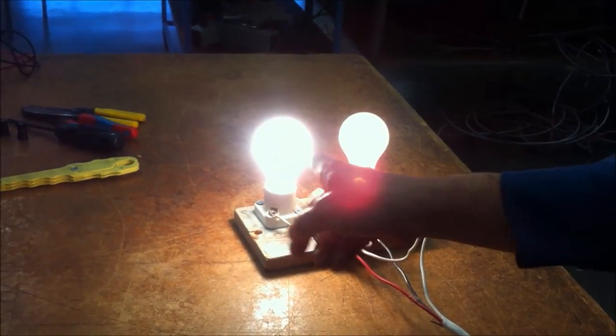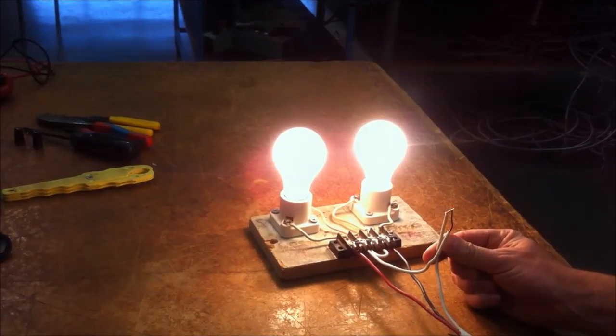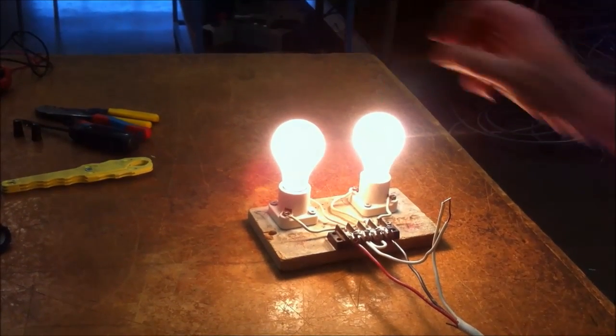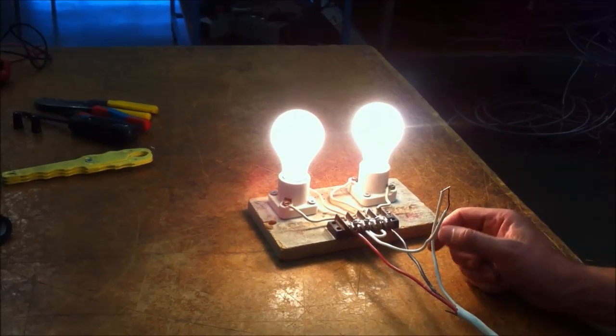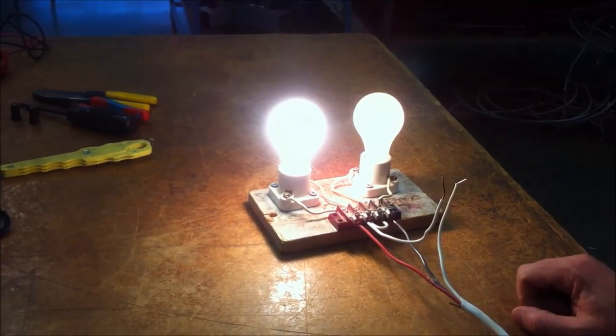This one's getting high voltage. It's 240 volts directly across both lamps. This way, it's 120 volts on each lamp under normal conditions. An open neutral places a much higher voltage on one lamp, much lower voltage on the other.